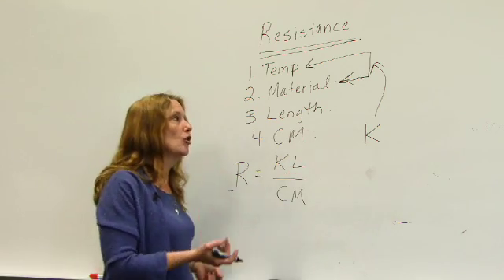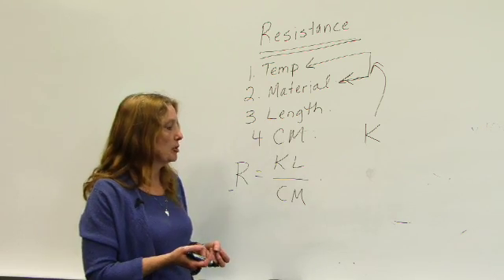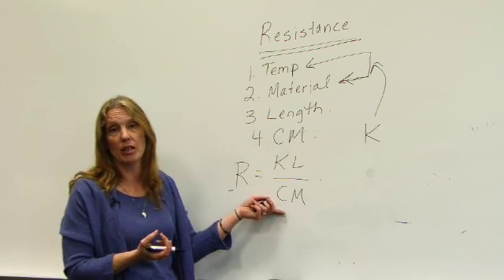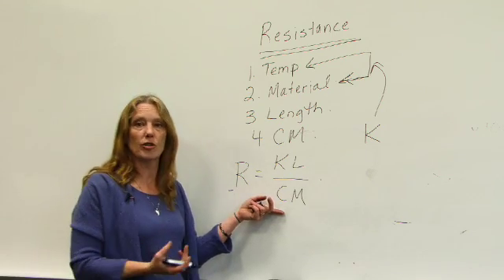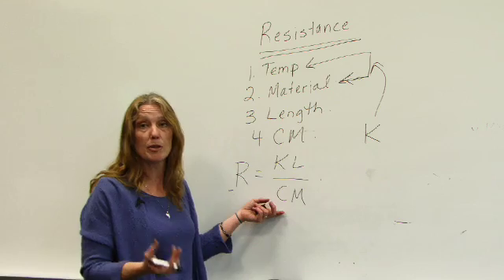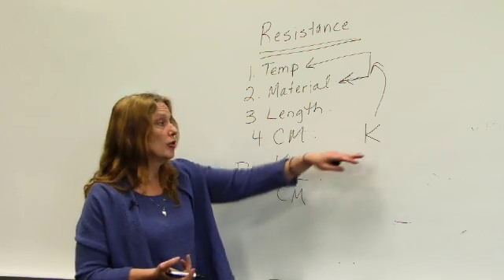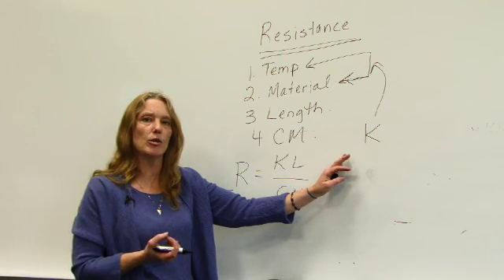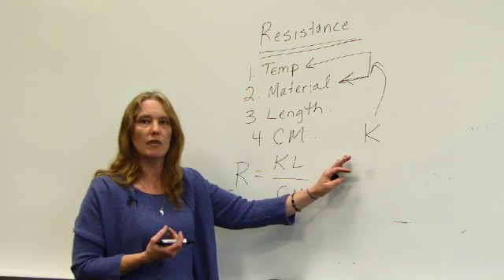Now using the code book for an example, I can go to Table 8, Chapter 9, and Table 8, Chapter 9 is going to give me circular mill areas. It's going to show me how many circular mills a number 12 gauge wire is, how many circular mills a number 10 has. It's also going to give me kind of like a K value. It's going to give me a resistance value per thousand feet of wire.